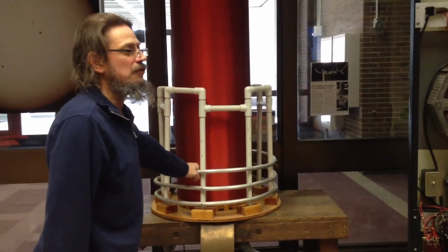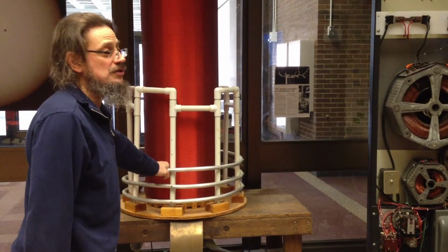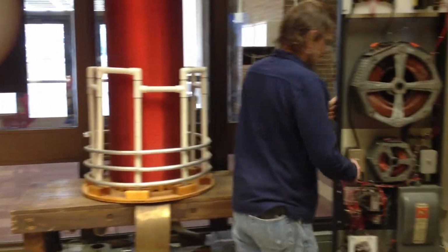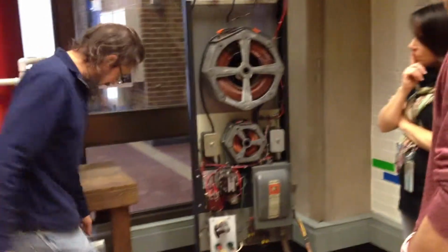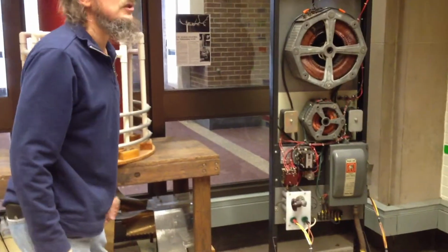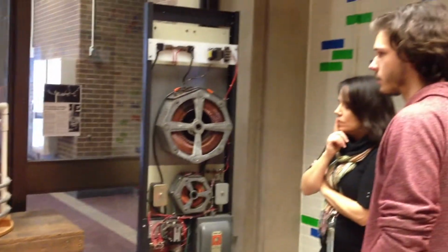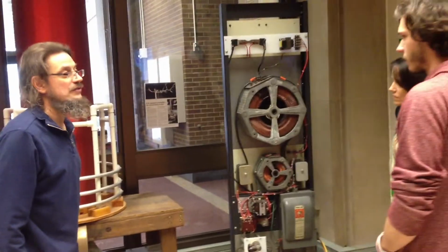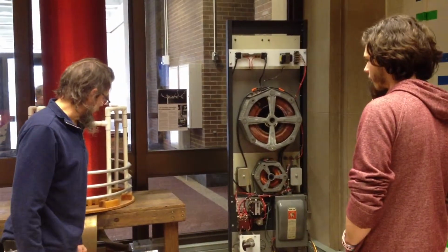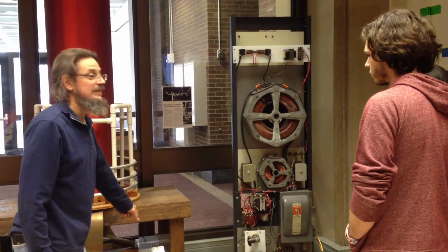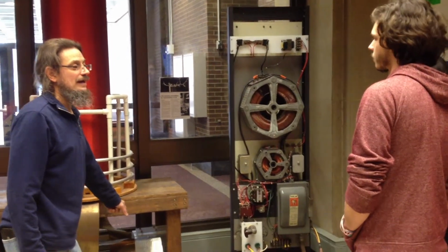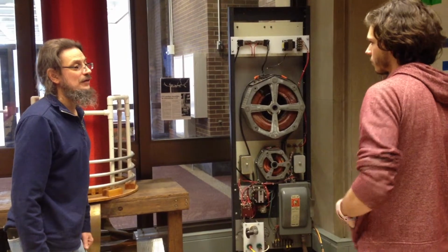And it ultimately allows the current to flow and takes it away. It essentially chops it up, at the rate determined by the RPM that the motor's spinning. So why are you wanting it to chop up? Well, we have to generate high frequency. See, the line current is only 60 hertz, and we need 650 kilohertz. So by spinning this, it takes that 60 hertz and chops it up to 650 kilohertz.